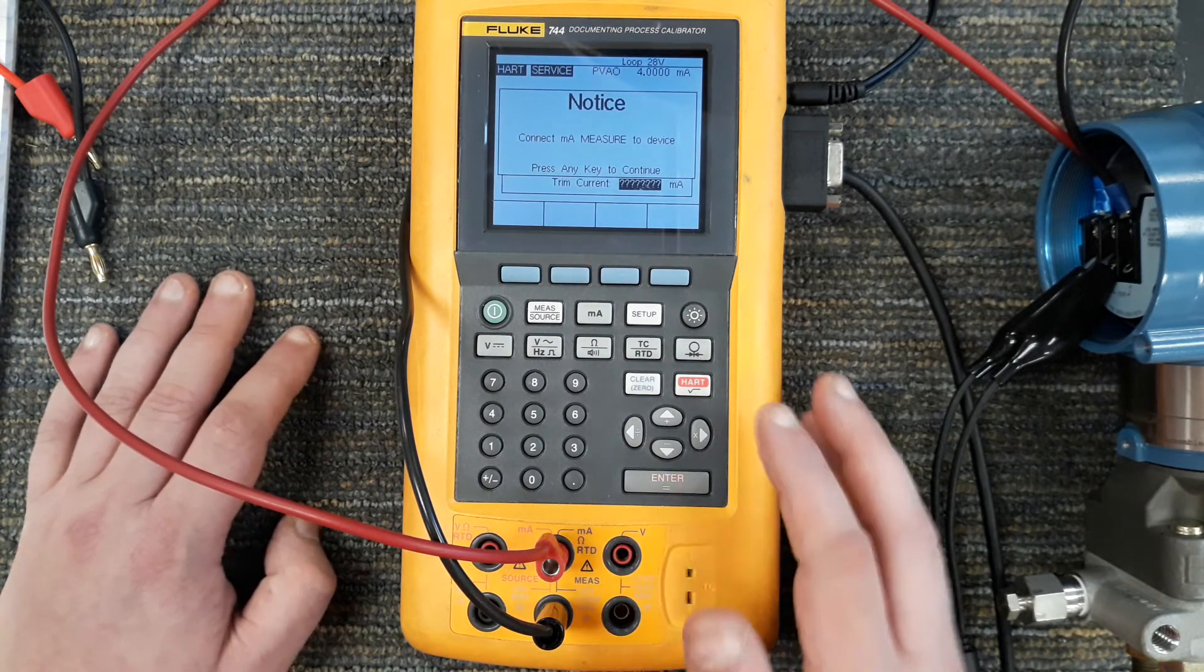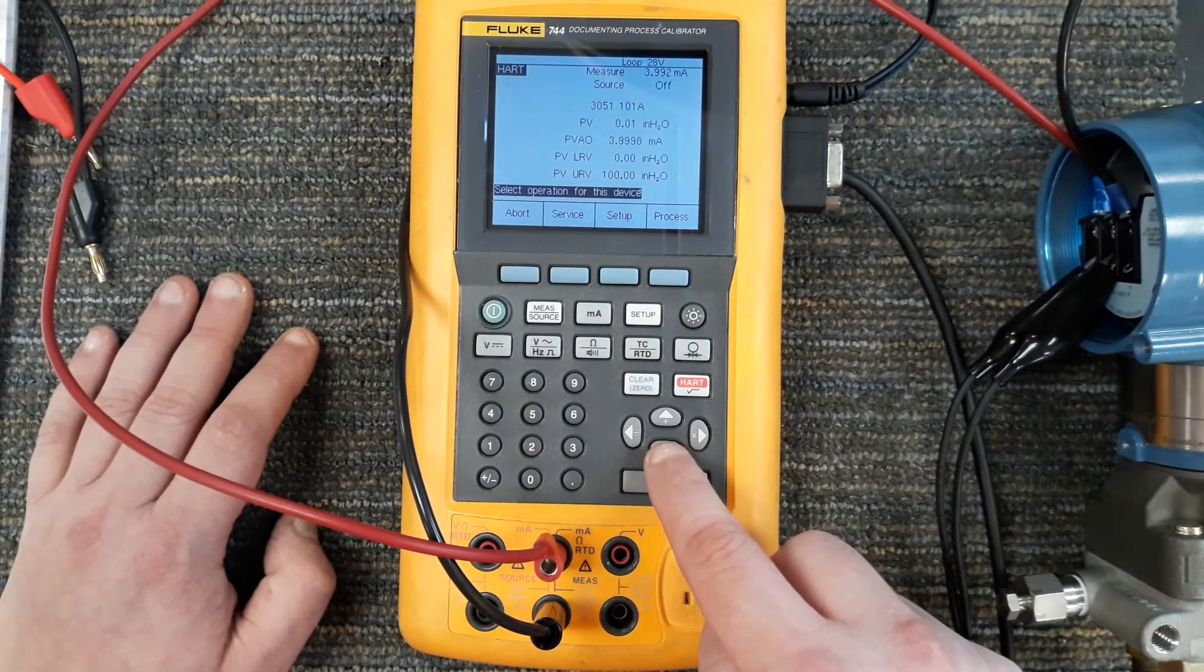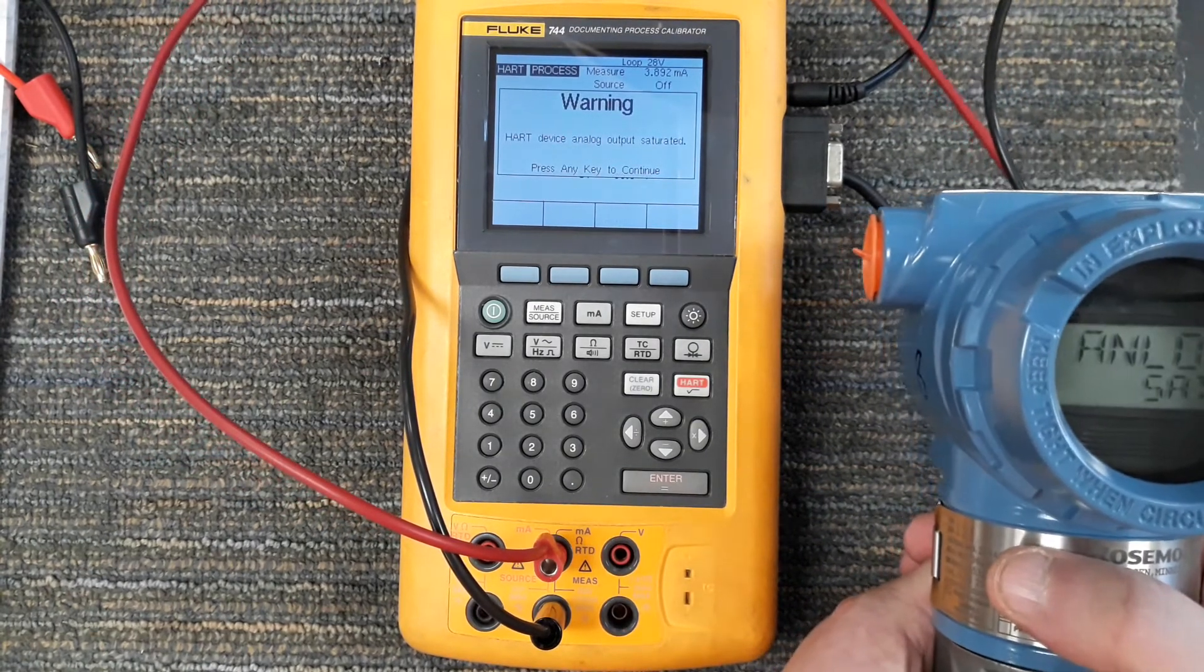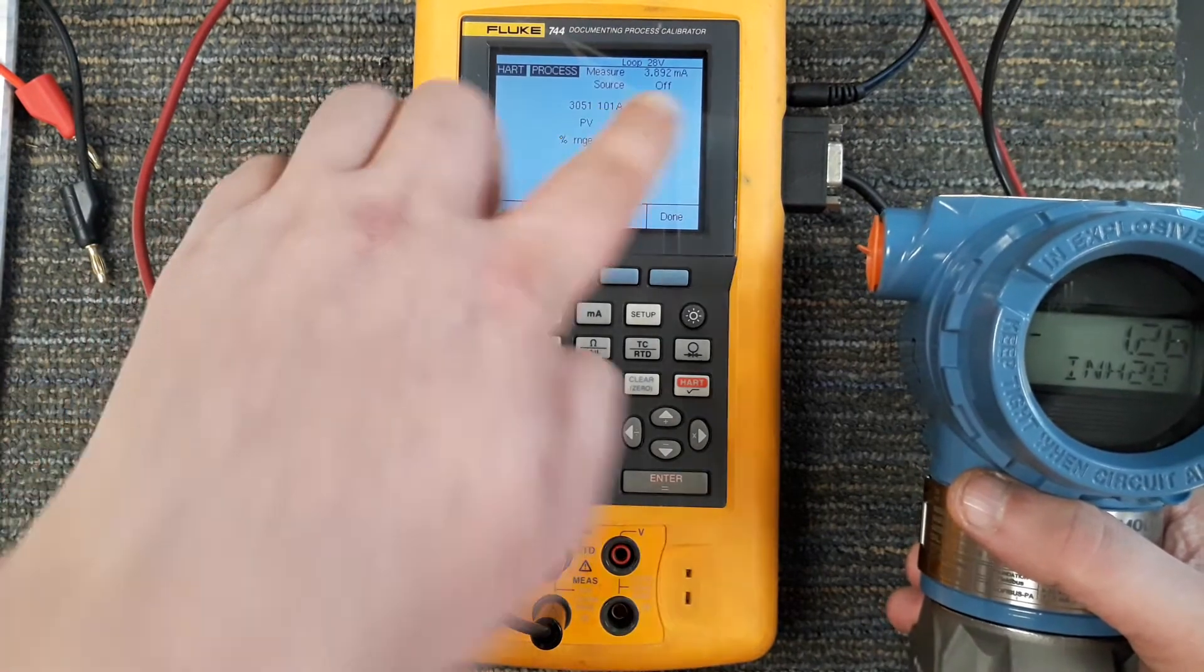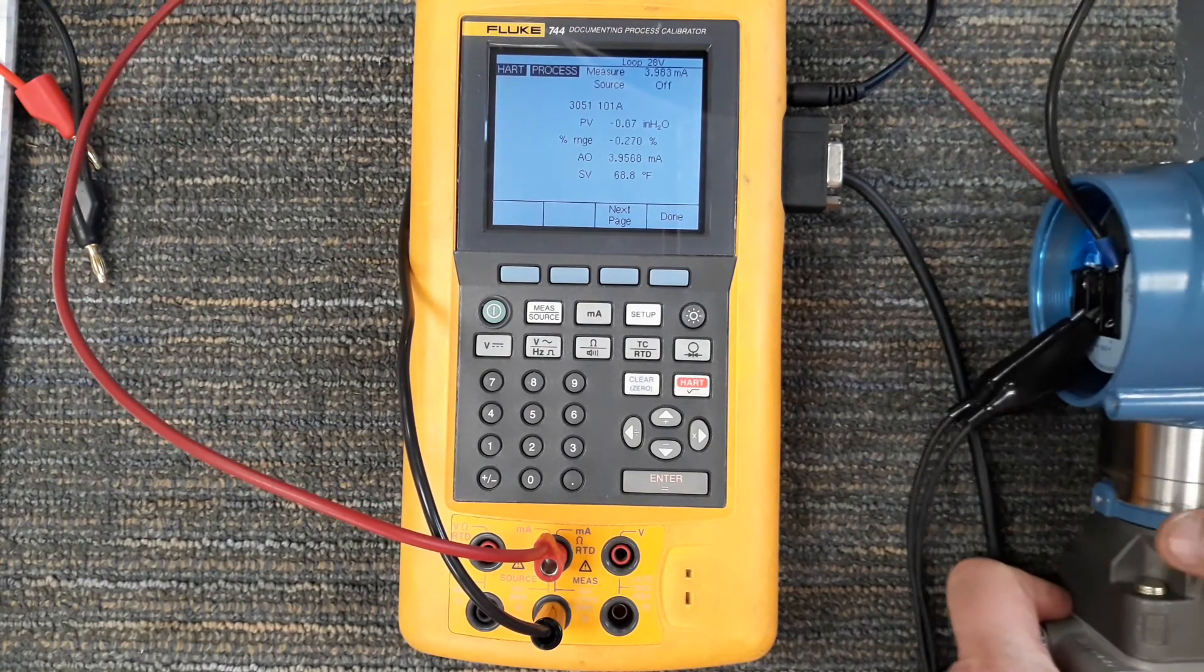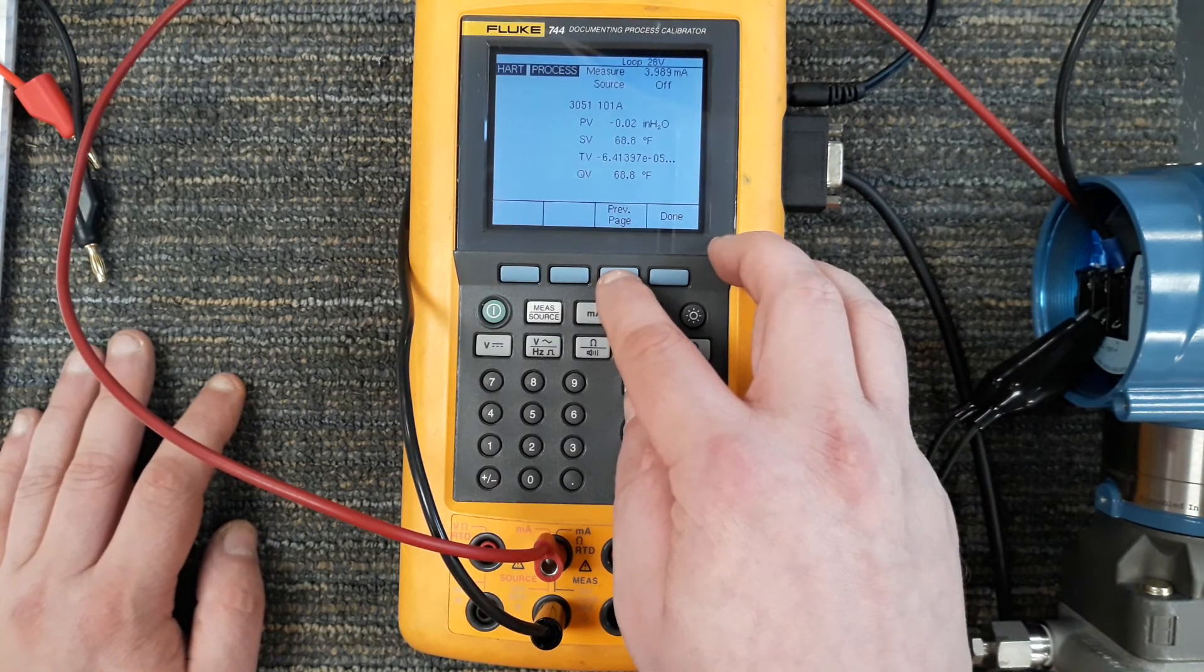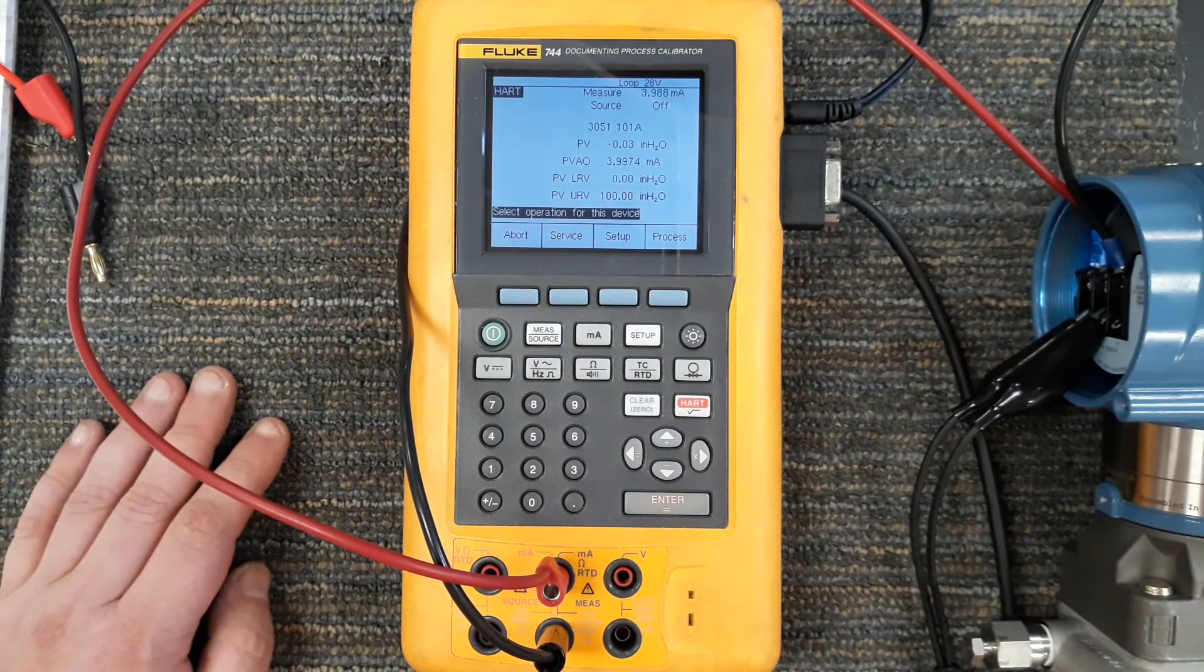We went into the service, we had setup. Let's go into the process and it's just giving me readings, which was kind of like what the display on this thing was telling me. It says negative 1.26. This is below zero inches of water column, that's because I raised it up. That's your standard walkthrough of how to use this as a communicator with the demonstration with the Rosemount 3051 differential pressure transmitter.